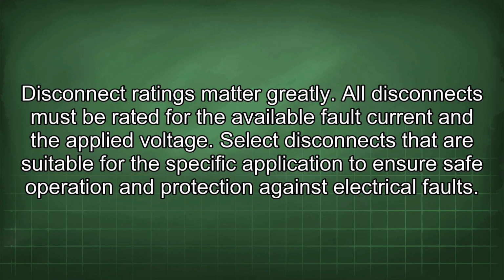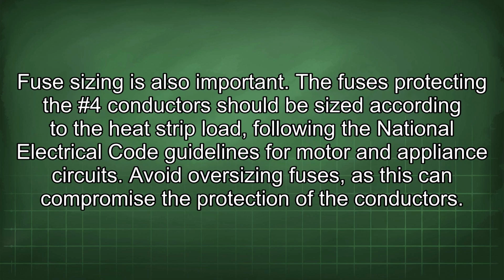Select disconnects that are suitable for the specific application to ensure safe operation and protection against electrical faults. Fuse sizing is also important. The fuses protecting the #4 conductor should be sized according to the heat strip load, following the National Electrical Code guidelines for motor and appliance circuits. Avoid oversizing fuses, as this can compromise the protection of the conductors.